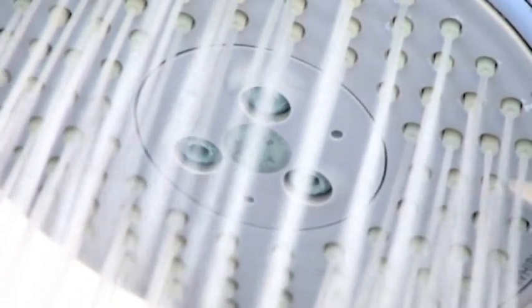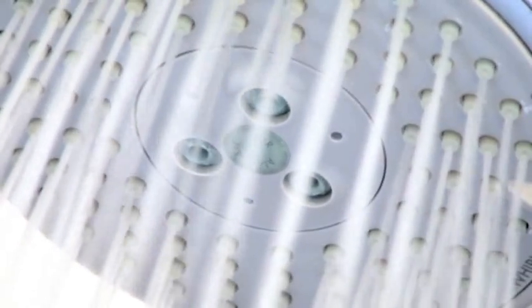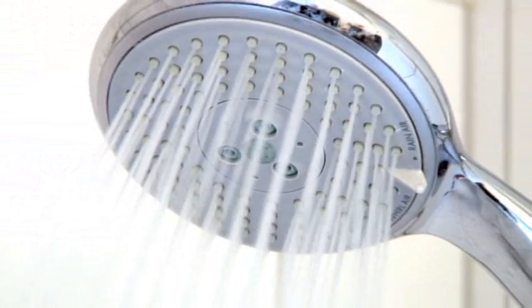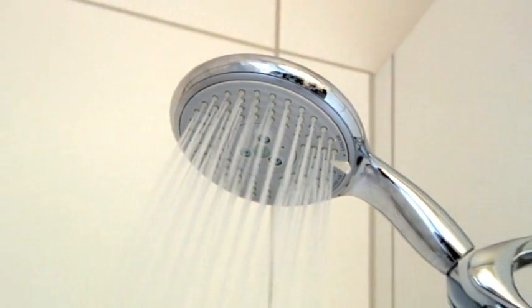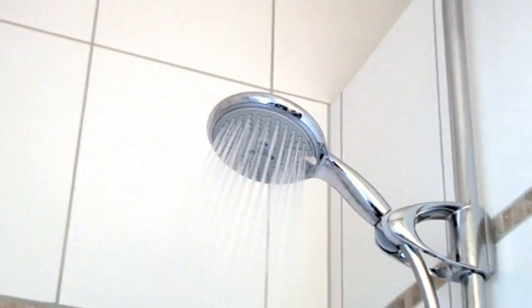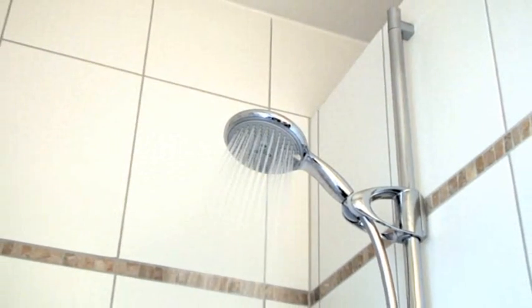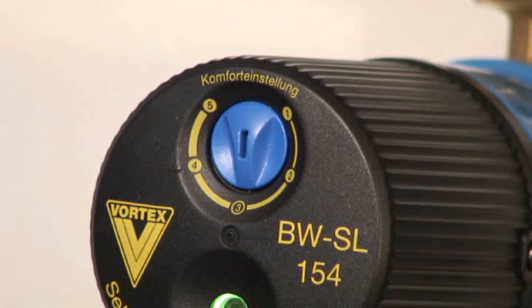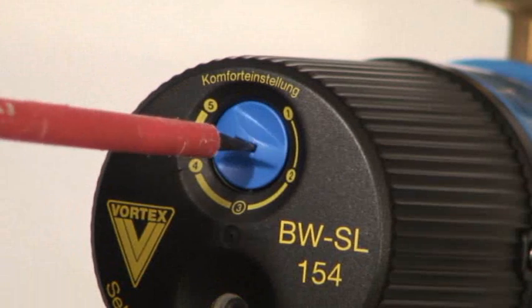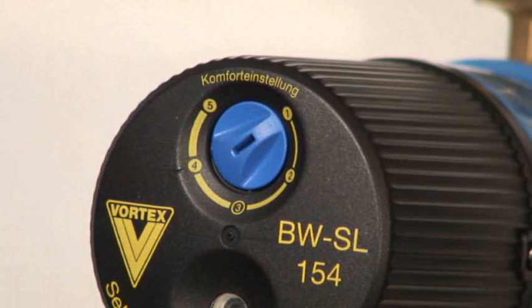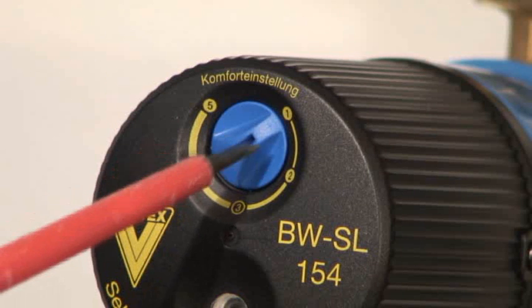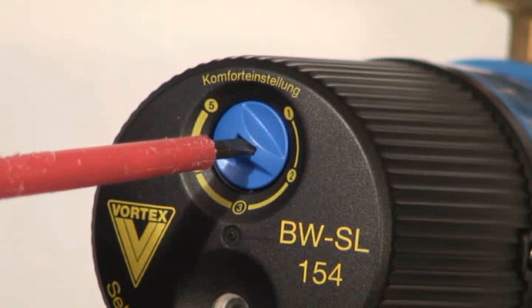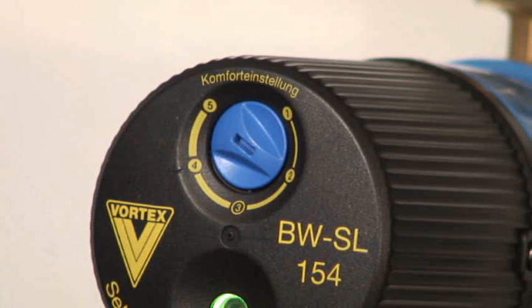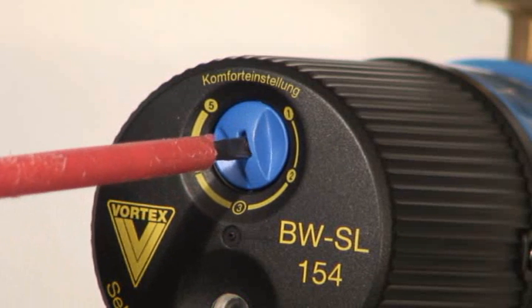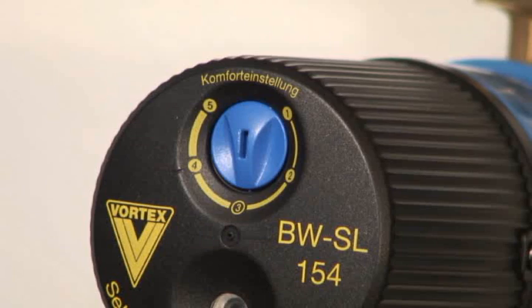Our BW-SL154 automatically recognizes a disinfection run, triggered by the boiler control system. In principle, there are no settings to be done. Switch setting 3 provides a good level of comfort and low energy consumption. And the BW-SL154 can be infinitely regulated as well. We offer the best possible predictive technique for the provision of hot water.